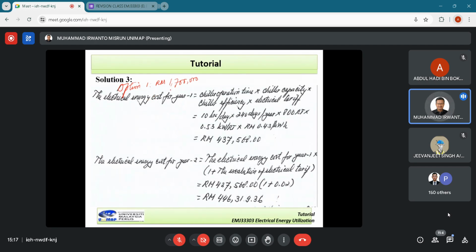Now we know the energy is given by power multiplied by time. And power here, we know the efficiency of the chiller equals power consumed in kilowatts divided by RT. So from here, we can write power consumed in kilowatts equals efficiency of chiller multiplied by cooling load in RT. This is power.